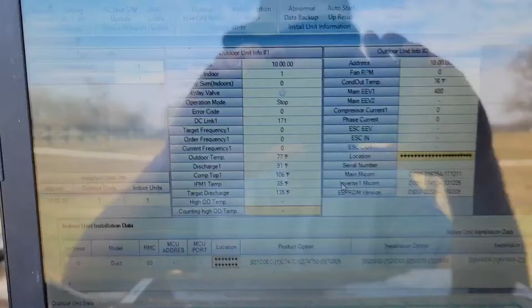Now you know that your indoor unit has option codes. If you haven't seen me write an option code for an indoor unit, check out my playlist, HVAC Tips for Technicians. I've got videos where Samsung units were overheating, and I had to input an option code, called fan thermo on or fan thermo off, to make it stop overheating and turn the indoor fan. You've also seen me change fan speeds using this SNET tool.